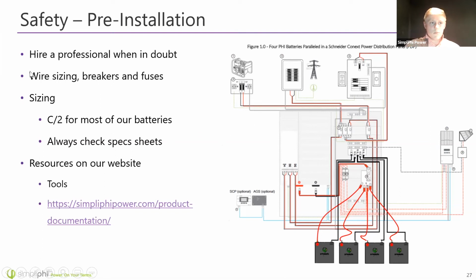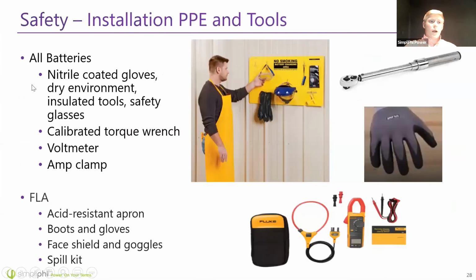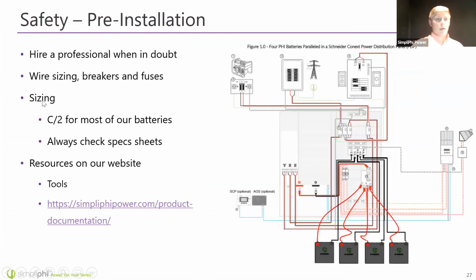Professional installers are definitely going to know about wire sizing and fuse and breaker sizing, and where those are required. Breakers and fuses are always a great idea to add safety to a system, and they're likely required at several points to protect the components. It's also always a good idea to upsize wires from the minimum requirement.